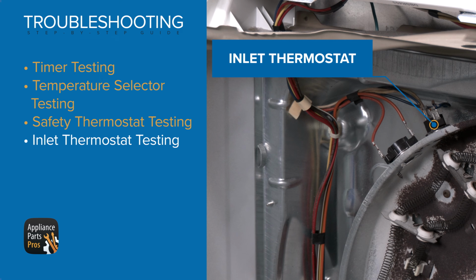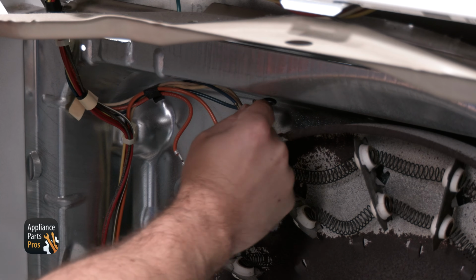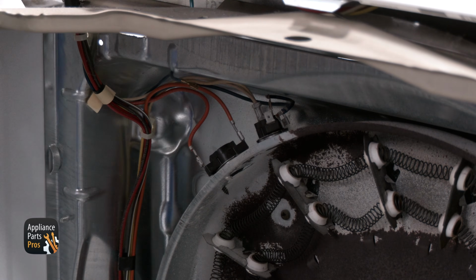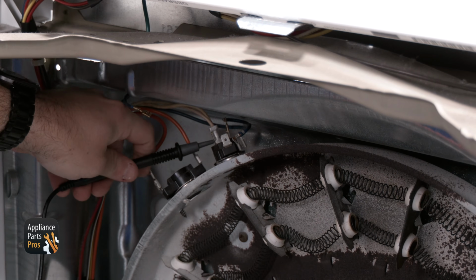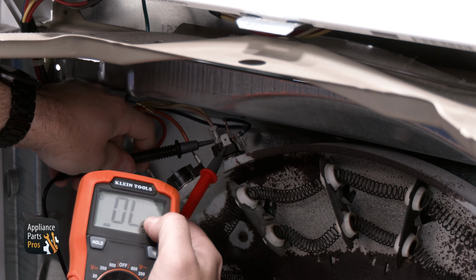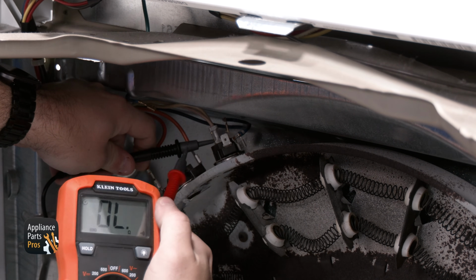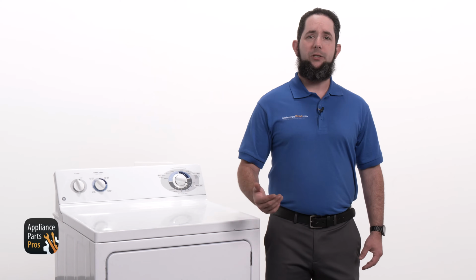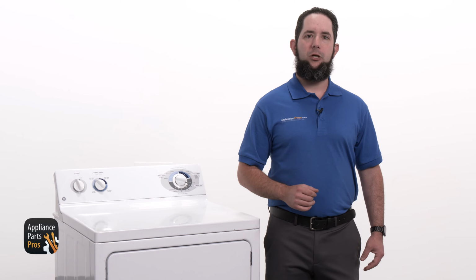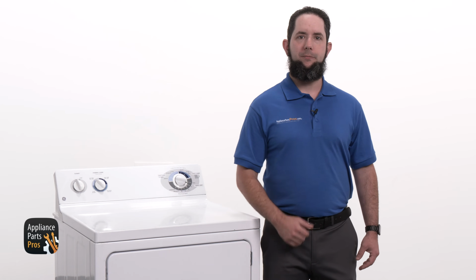The inlet thermostat is next to the safety thermostat, second from the left, and we're also going to test this for continuity. First, remove the leftmost wire and the outer center wire. Then place one probe on each. If you don't get continuity here, then the inlet thermostat has failed and will need to be replaced. If there is continuity, that means the thermostat is good and we'll need to continue troubleshooting.